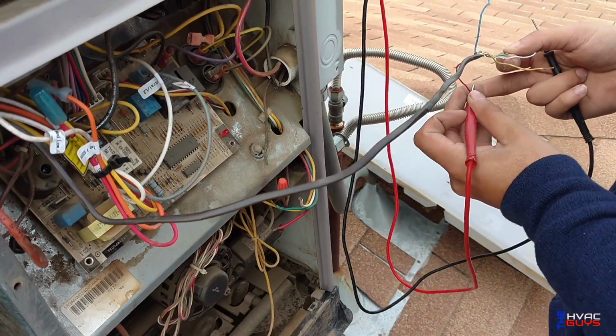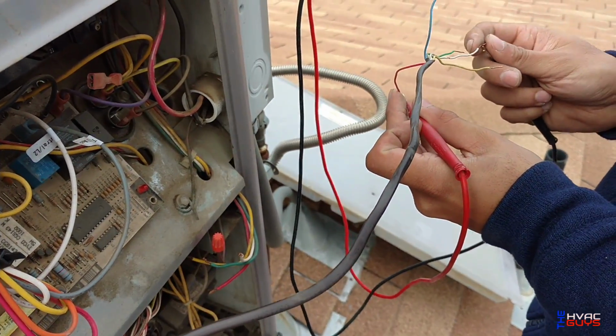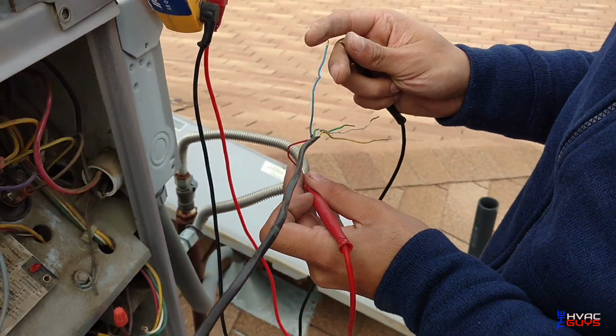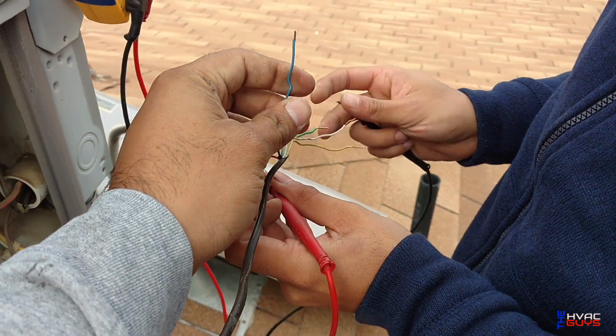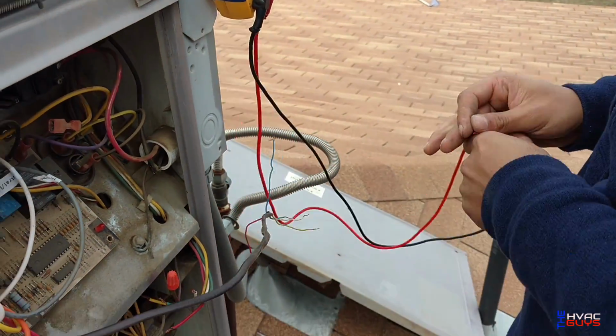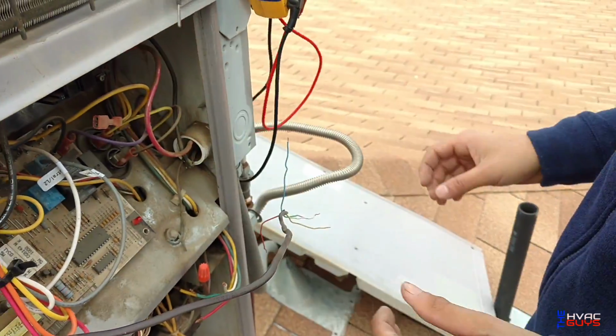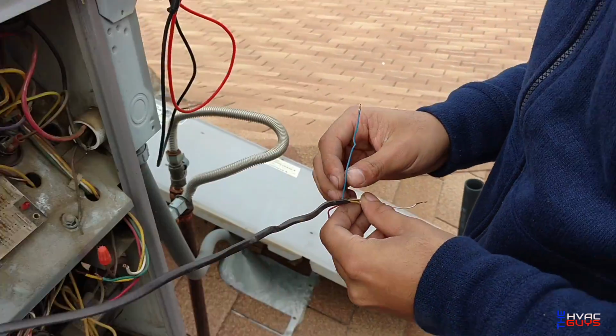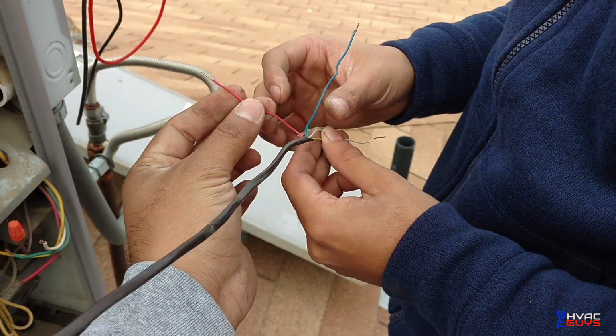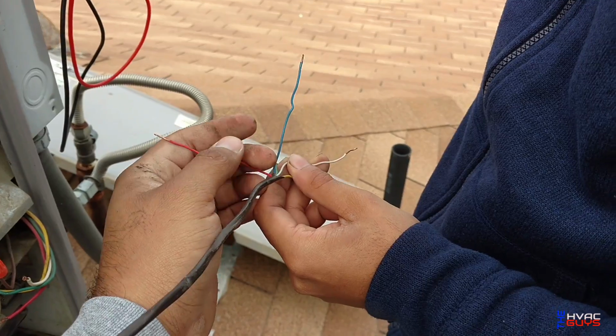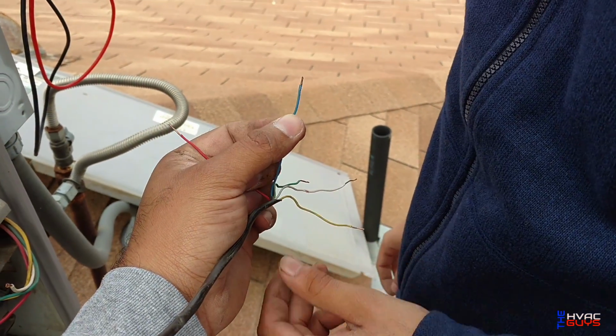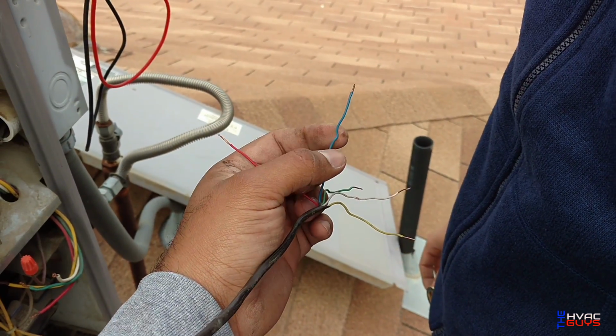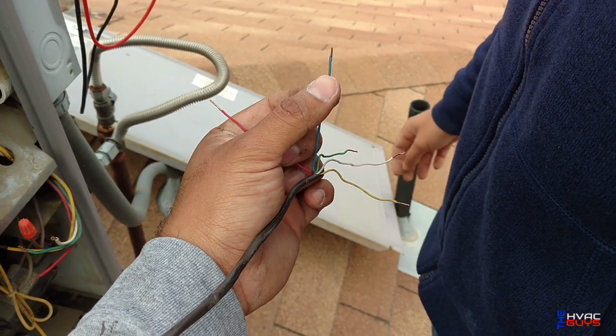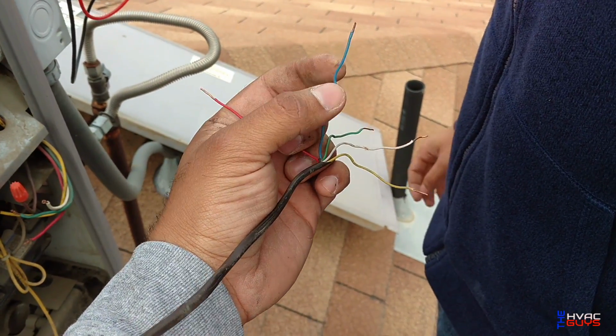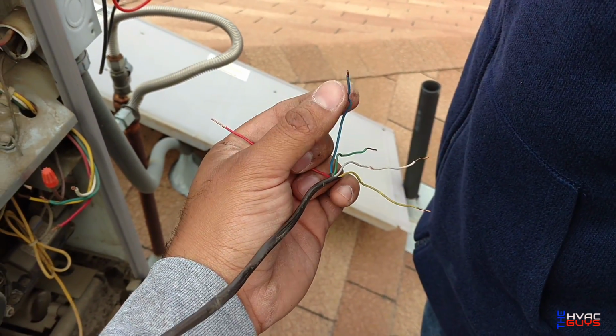Okay guys, as you saw, I eliminated that. The blue wire was hooked up to B. B is usually used, I think, on heat pumps to energize your reversing valve. So what was happening for heat, red was energizing blue and B on the thermostat, so that's why it was sending 24 volts. But this one was hooked up on the common, so that's why it blew out our fuse.